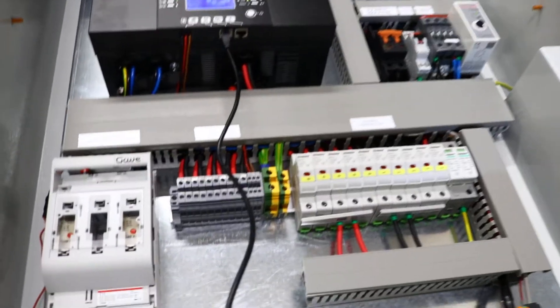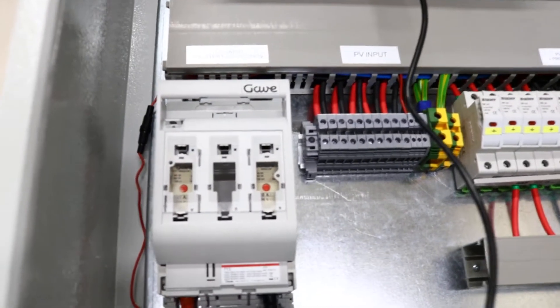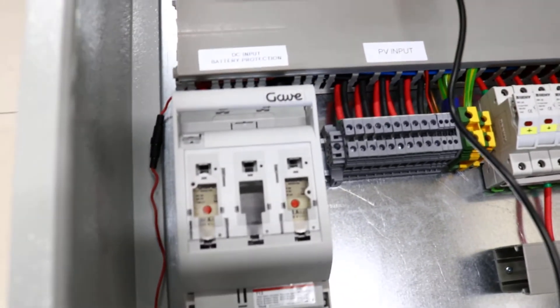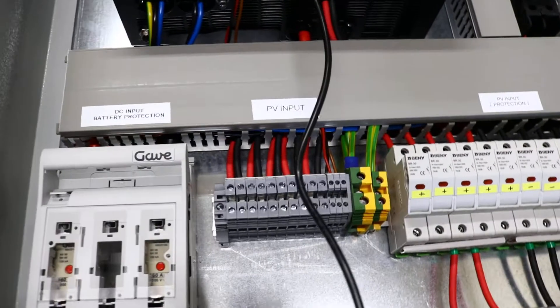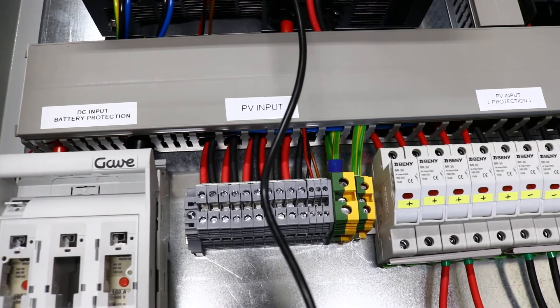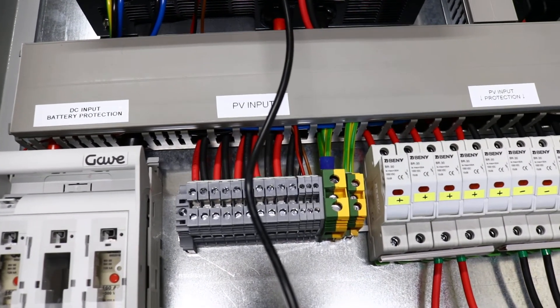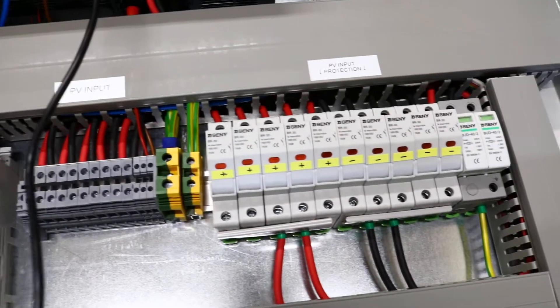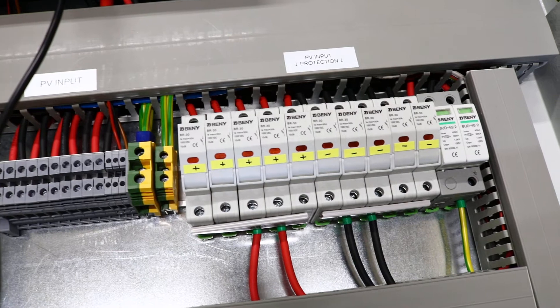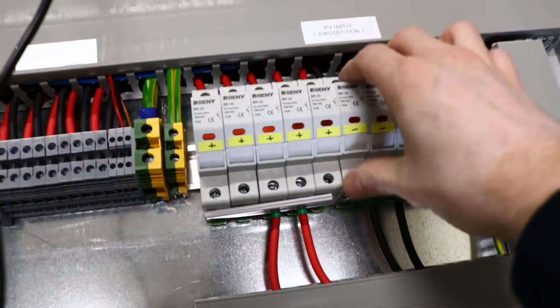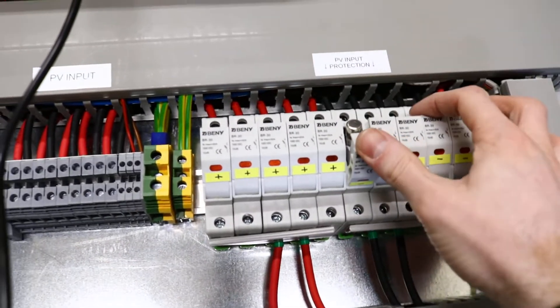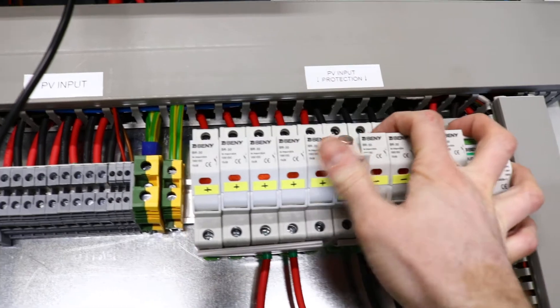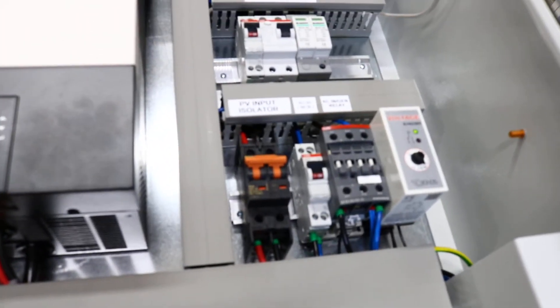As you can see, we have disconnect fuses to protect the batteries and the user. The PV input is up to 4.5kW, with string fuses rated at 15A and a DC disconnector.